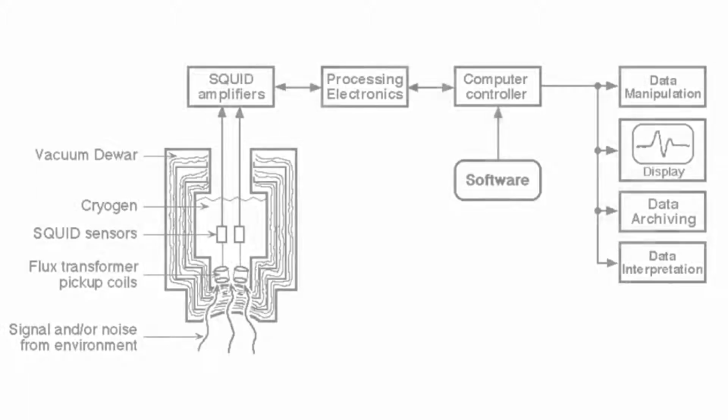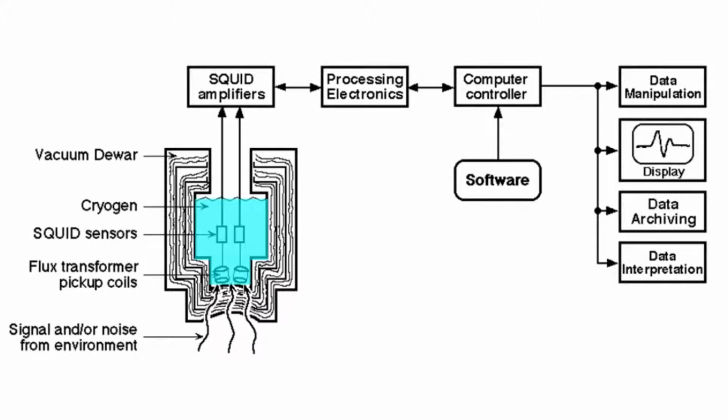Now let's take a look at the MEG system from a wider point of view. The largest bulk of the system consists of a large dewar containing the liquid helium for cooling down the flux transformers in the SQUIDs. From the SQUIDs on, the measured signal is amplified and then digitized and passed on to computers for display, storage and analysis.